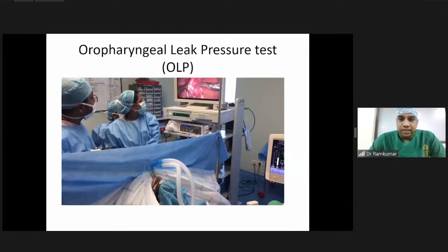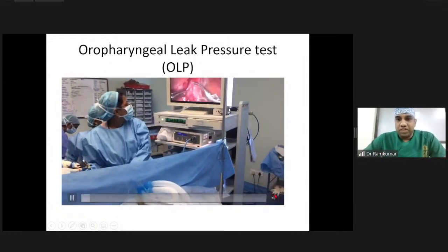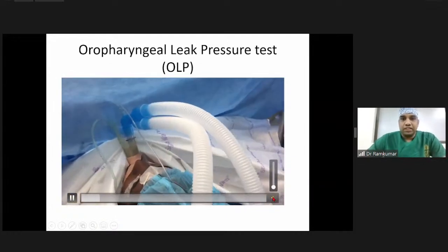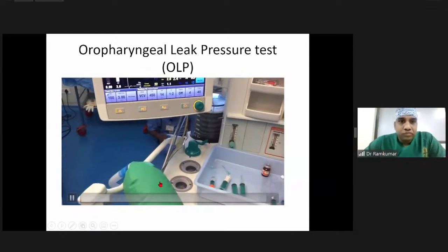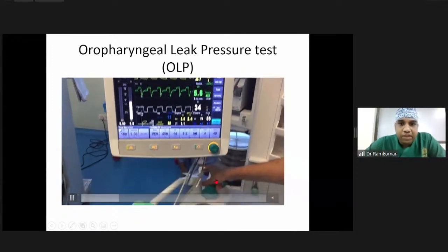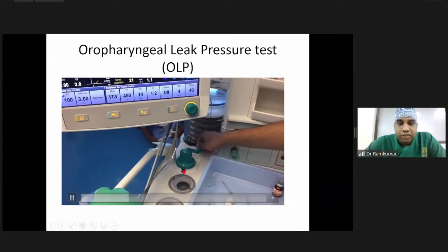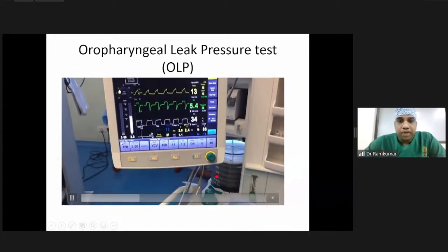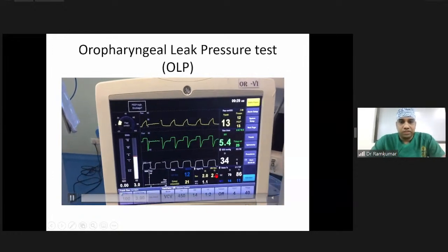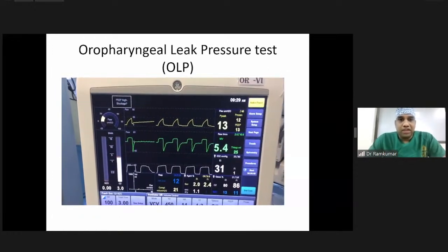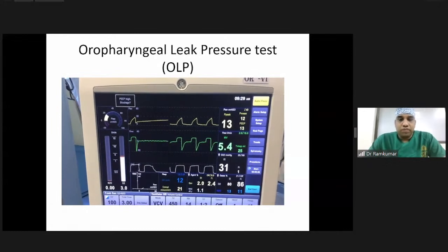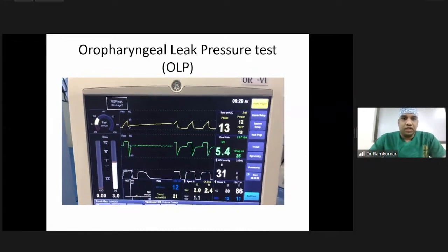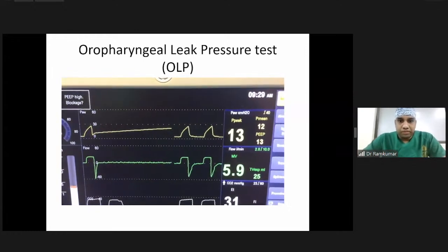How is it tested? This is how it's done. I'm showing an assessment of oropharyngeal leak pressure in the middle of a laparoscopic surgery, because if it leaks in the middle of the surgery, then it's going to be difficult to intubate or manage the patient. Here I'm using a ProSeal. 3 liters of flow is kept. I'm closing the APL valve to 30 centimeters of water, and I'm going for an apneic period, that is, manual ventilation, leaving the system like that. So as the 3 liters of gas flows, there's going to be a rise in airway pressure, which is going to show an upslope here.